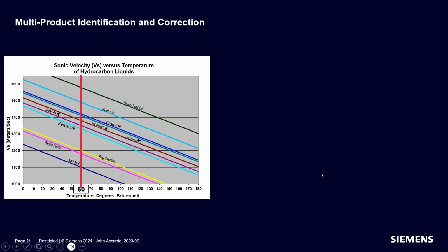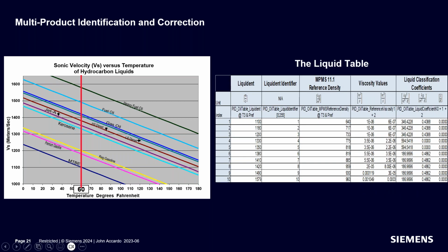It's what is the speed of sound. If I'm measuring 1400 meters per second and I'm at 60 degrees, what fluid am I seeing? It's low sulfur diesel, and it's unmistakable at that point. And so that's what a hydrocarbon meter will do. It will identify product through what we call a liquid table. And here's a liquid table. This is the 230 version.